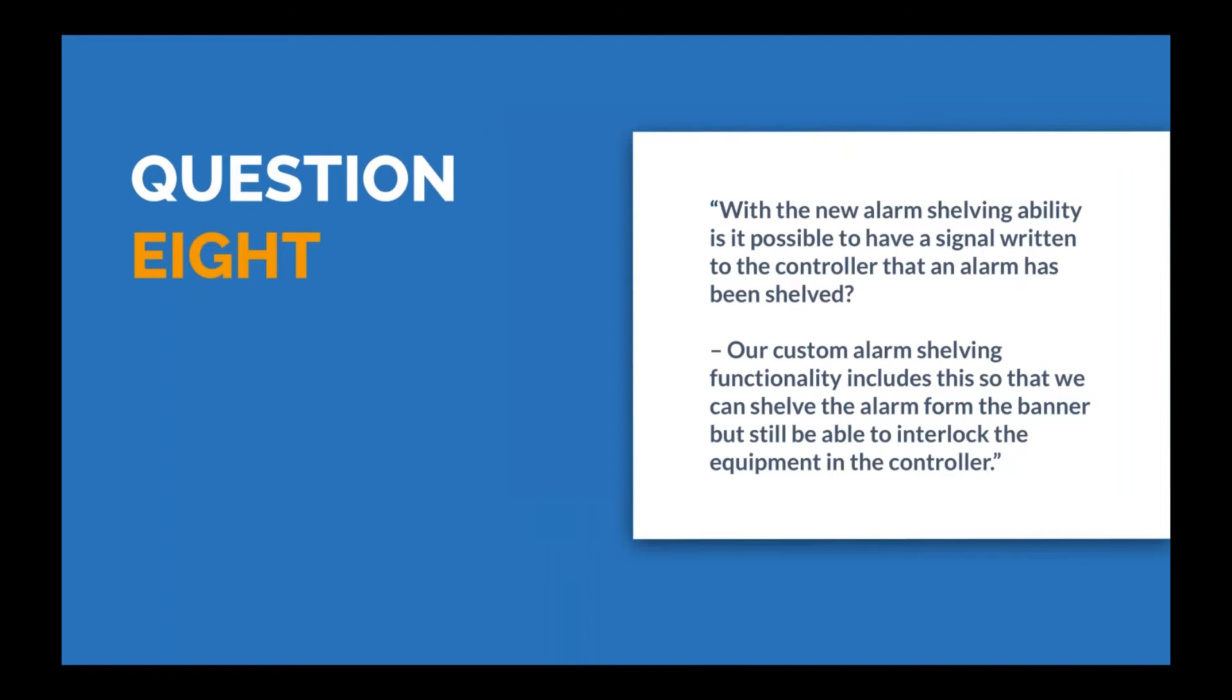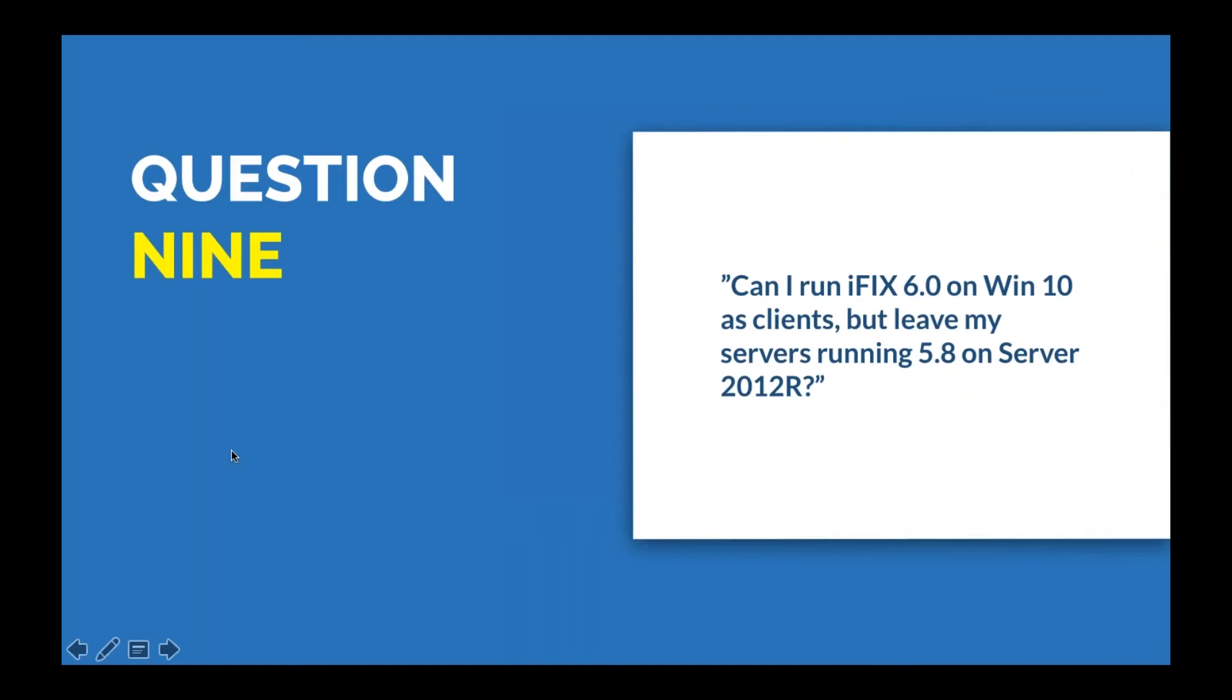A follow-up question asks what happens to shelved tags when the SCADA server is restarted. Dave believes they get reset but hasn't tested that thoroughly yet. Scott confirms he asked this question of the engineering team because it's come up before. Those are currently stored in memory. So if you happen to reboot the server or bring iFIX back up, the state returns back to normal, so they're not shelved anymore. They are looking at ways to enhance that capability to make those stay permanent, but yeah, they do go away.